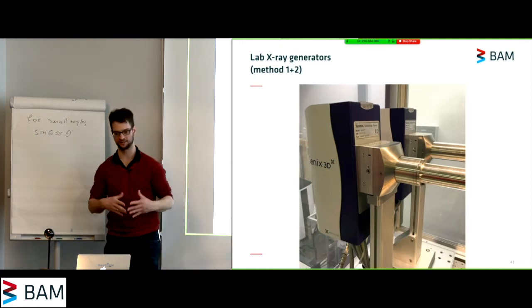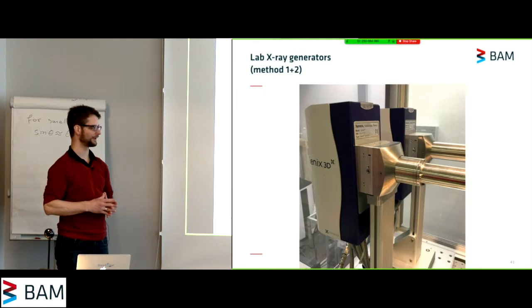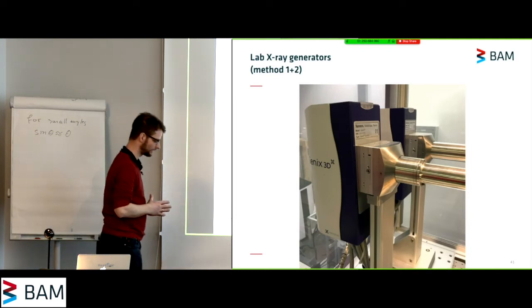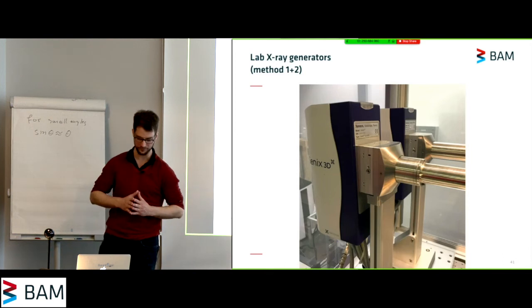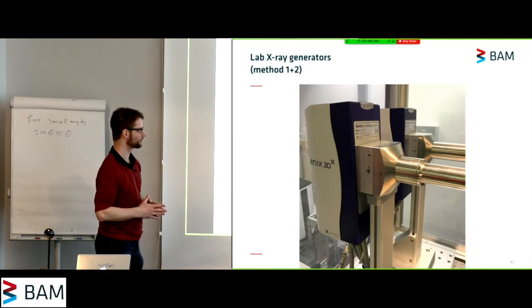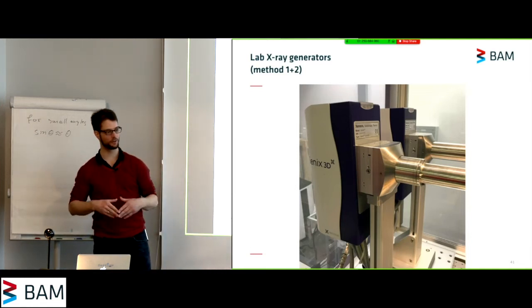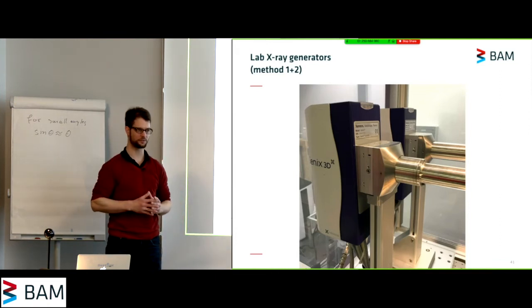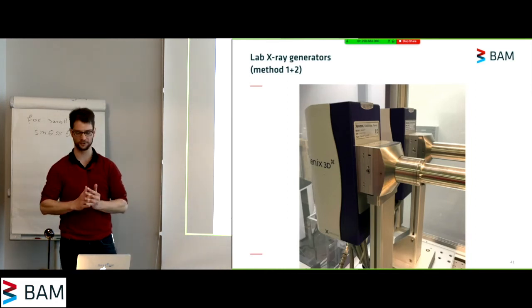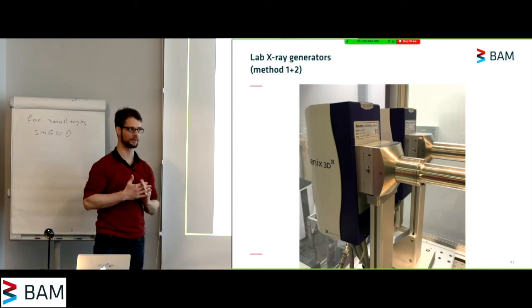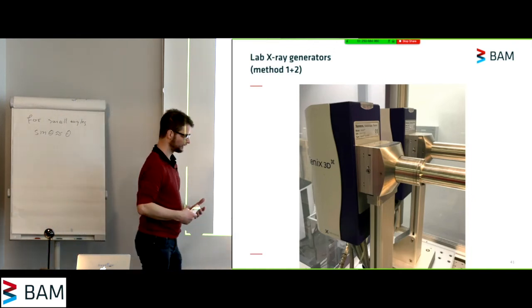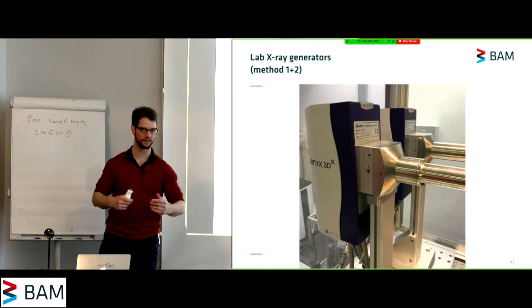So we switched these on two years ago, and they're still going quite strong. So we're really happy with not having to deal with maintaining the X-ray sources. Also, in the current environment, or with the current environmental problems, we're quite happy that we're not burning through so much electricity doing our experiments. We're still, over the course of a year, the whole instrument still takes 3.5 tons of CO2 equivalent in terms of electricity, so we still need to be a little bit careful about what we measure and how we measure and how efficiently we measure. But it's a lot less impactful than any of the other X-ray sources.